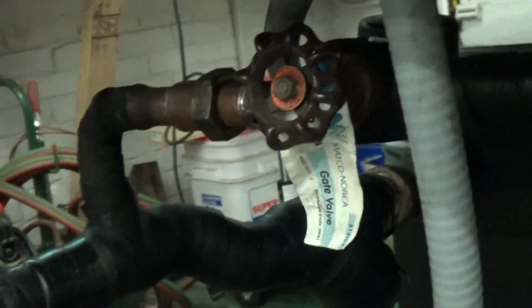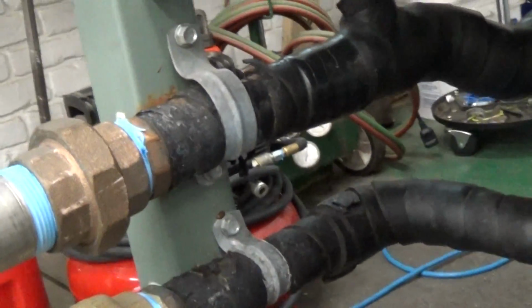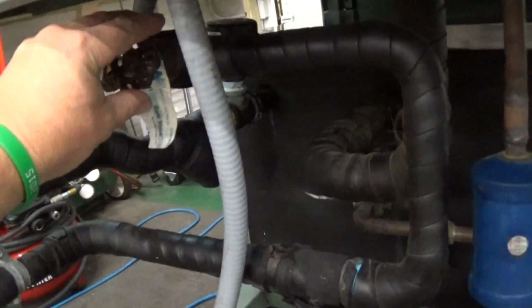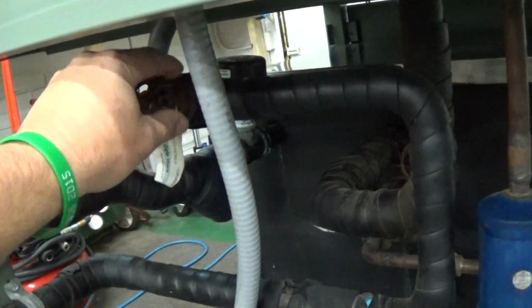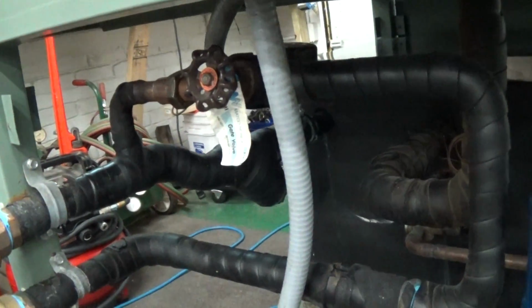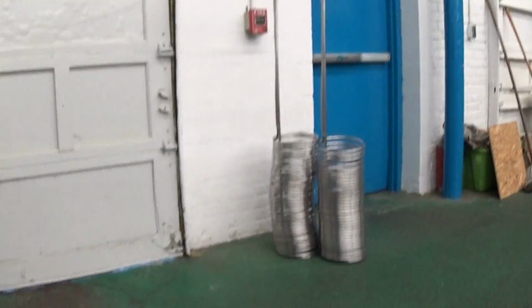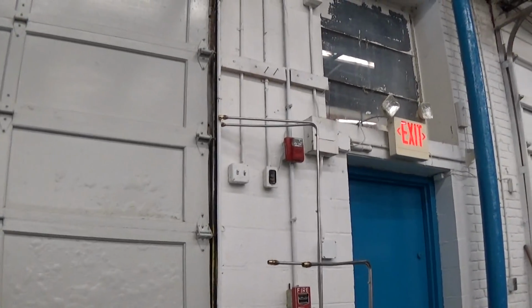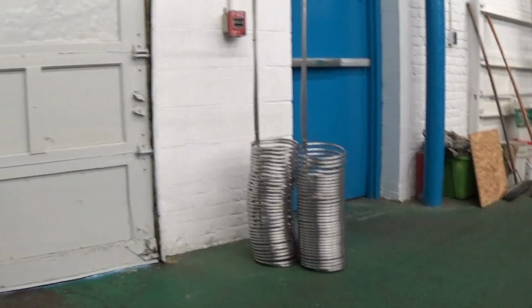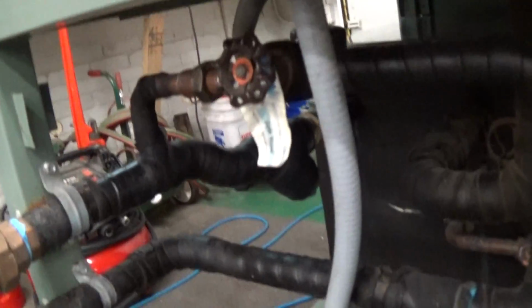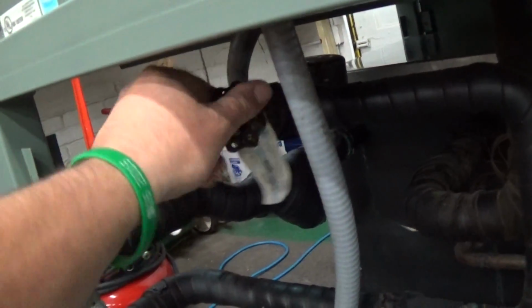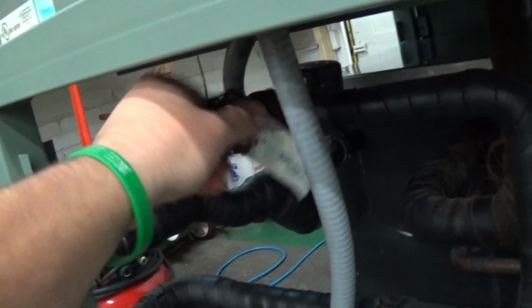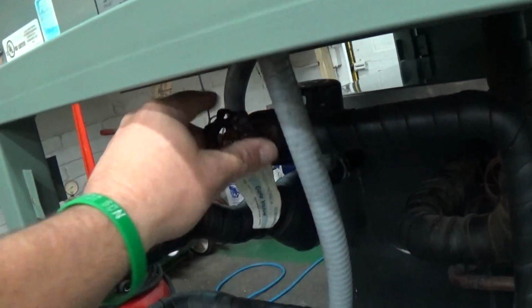Now, important here is that we also have this line here. This is your bypass. So you already have a bypass. You don't have to pipe in your own bypass out here. And if your flow is a little bit restricted on the coil heat exchangers, which we have over there, you can see one much taller than the other. Those are going to stack over each other. If that restricts the flow a little bit too much, you can crack this open. This is all the way closed. And then you might maybe crack it open a third of the way or so.